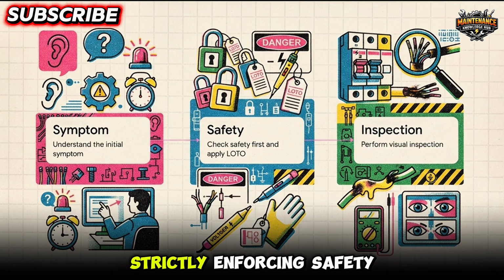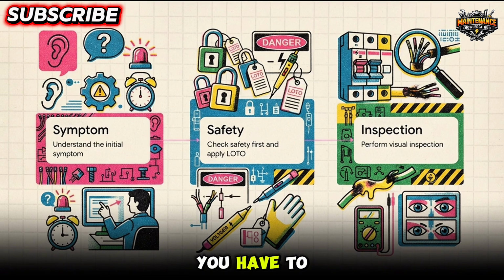Step 2 is strictly enforcing safety. You have to apply your lockout/tagout or LOTO procedures. Verify the absence of voltage with proper test equipment. Listen, this isn't just corporate policy. It is literally life or death. Never assume a circuit is dead just because some breaker is flipped off.